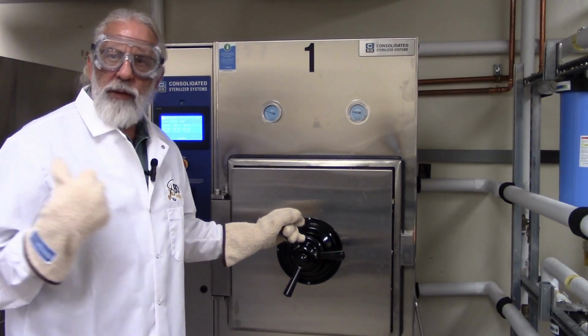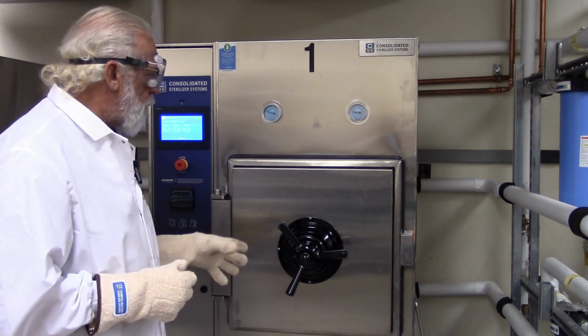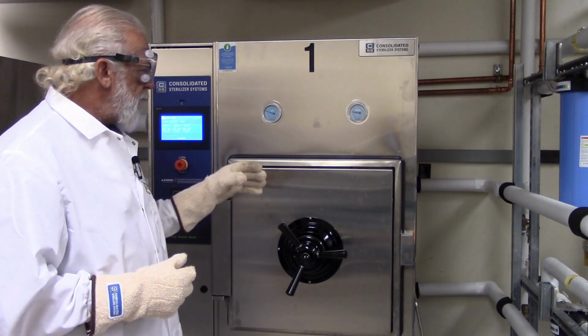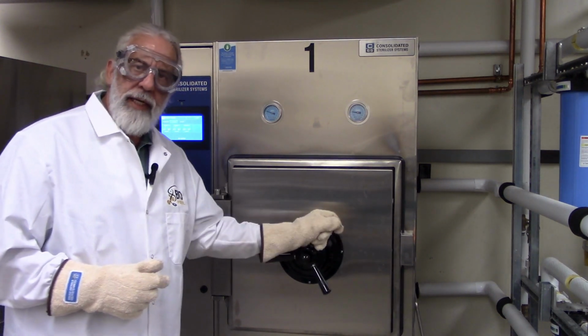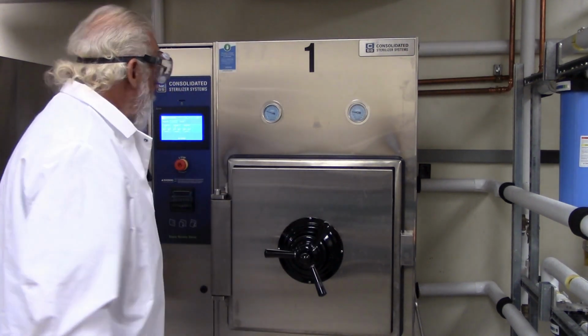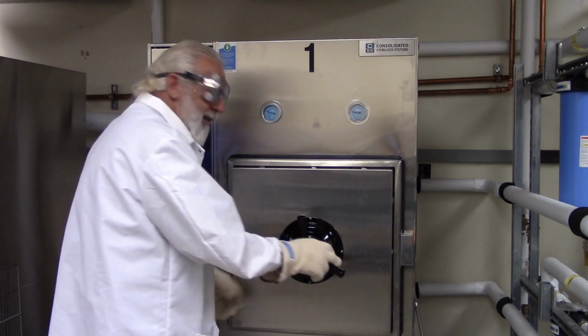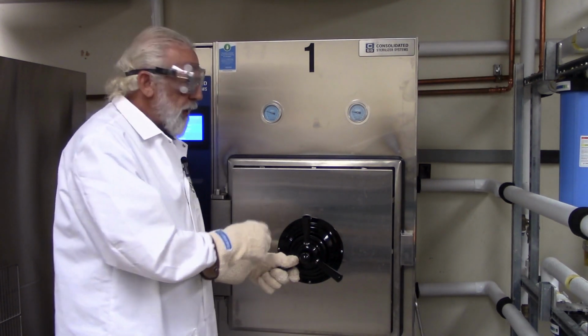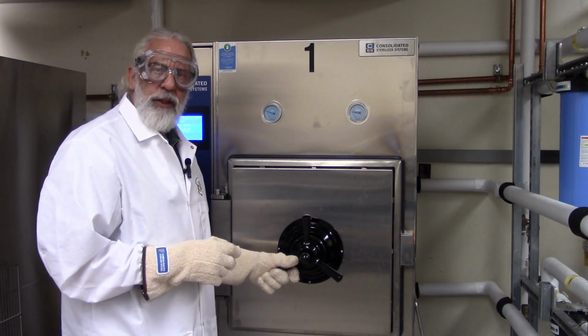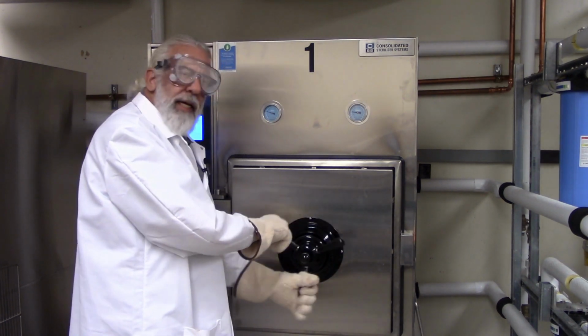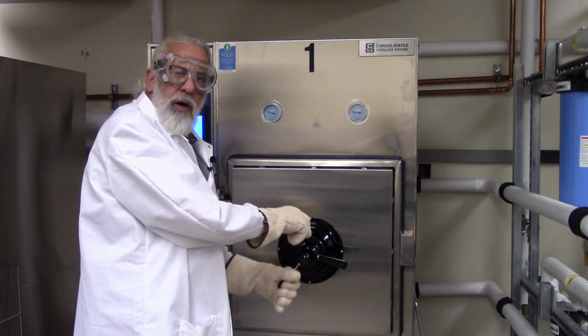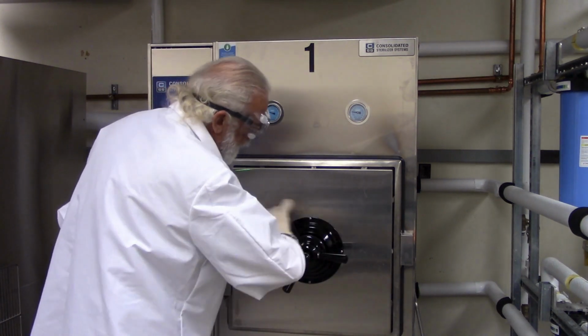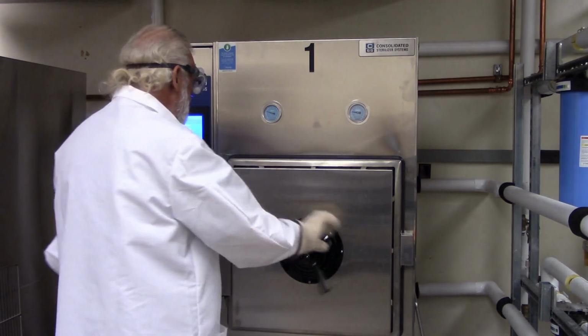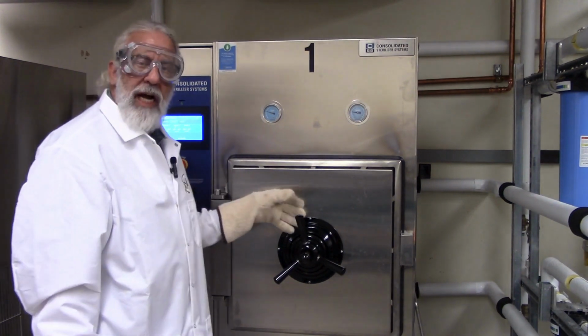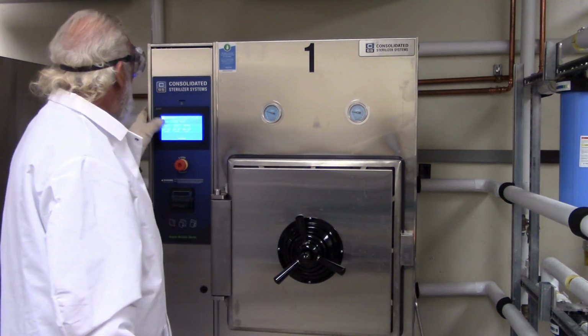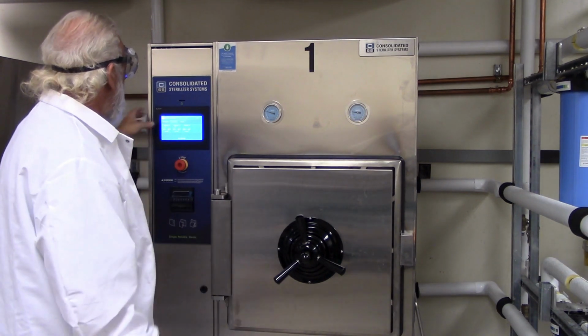While we're waiting for the other autoclave to run through its sterilization cycle, I did want to show a troubleshooting aspect of how to deal with some of these doors that have a wheel rather than doors that slide up and down. One of the things that can happen is that as the gasket ages, sometimes it's hard for some to get the door closed tight enough initially, which can create a steam leak at the beginning that some people are intimidated by. So let me show you what you'll need to do. It's not as dangerous as it may seem. I'm purposely not tightening the door quite enough, I think. I'm going to press gravity, one of our gravity cycles.